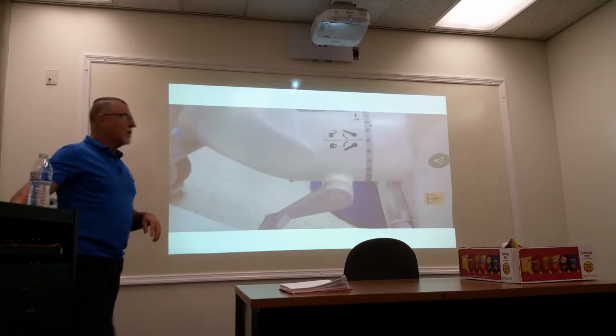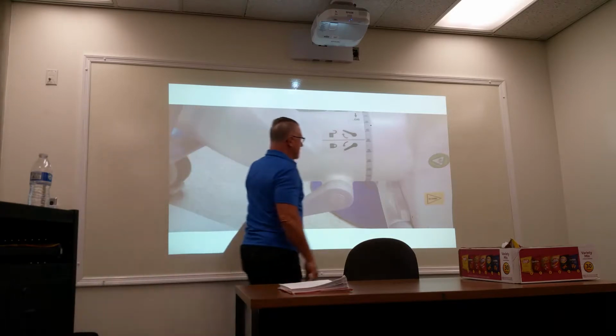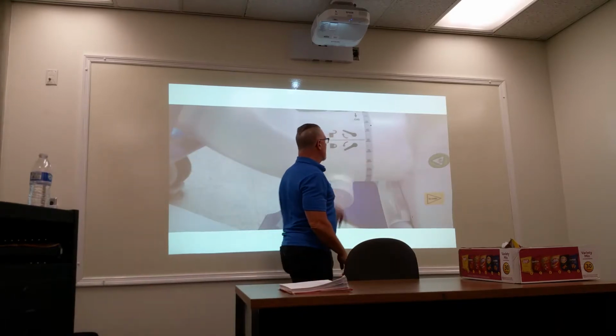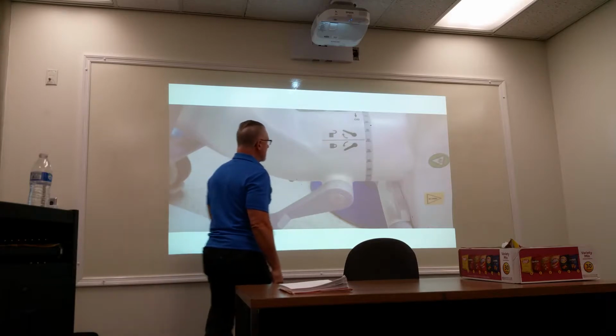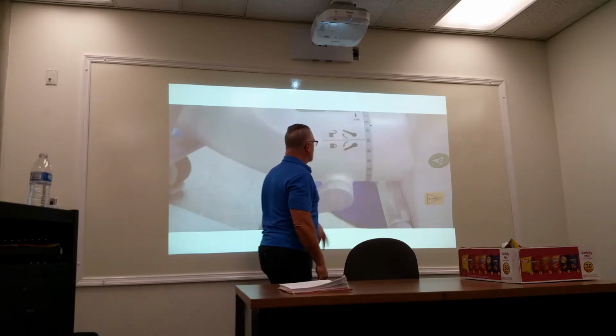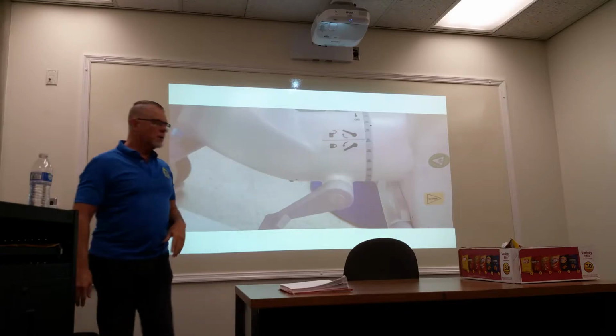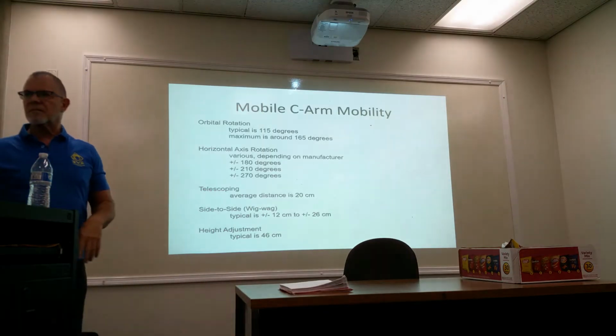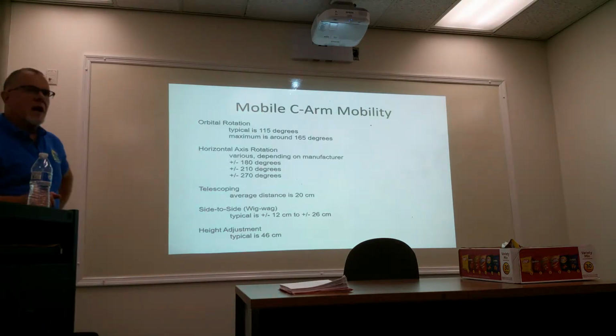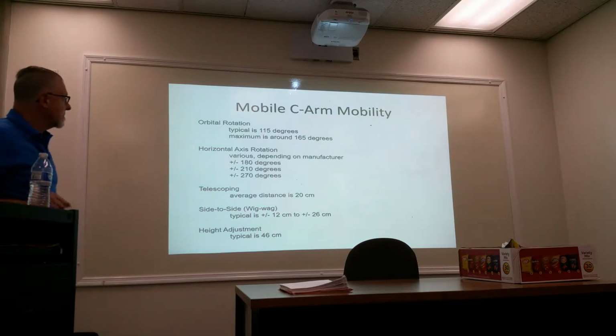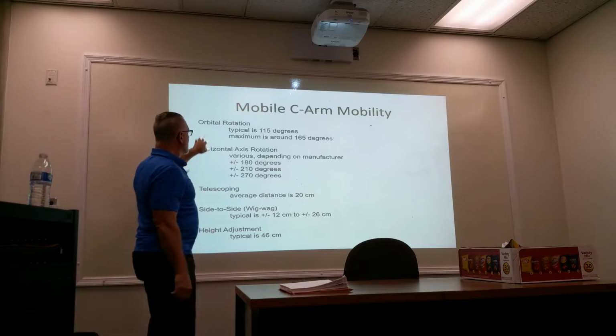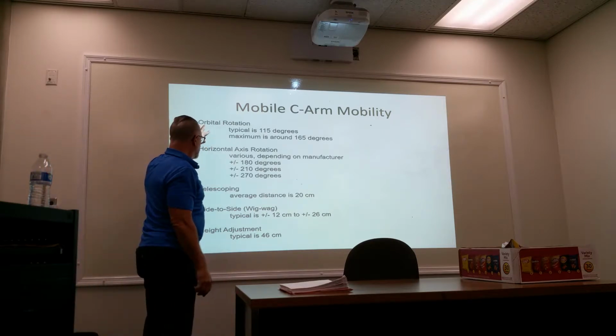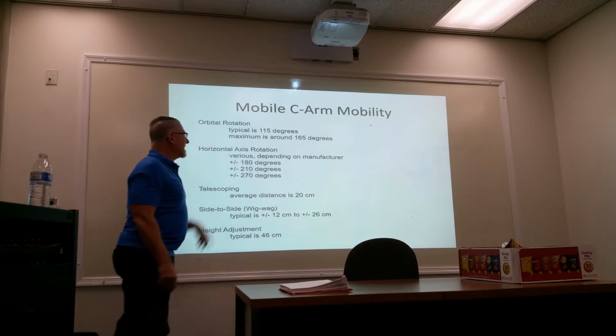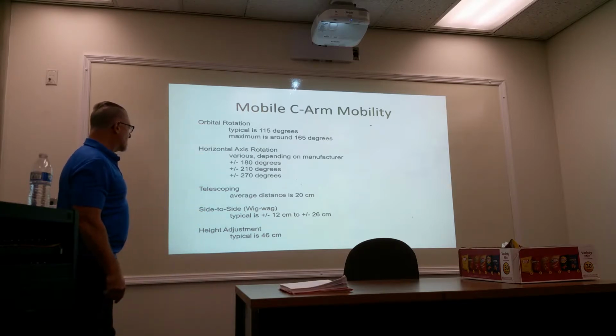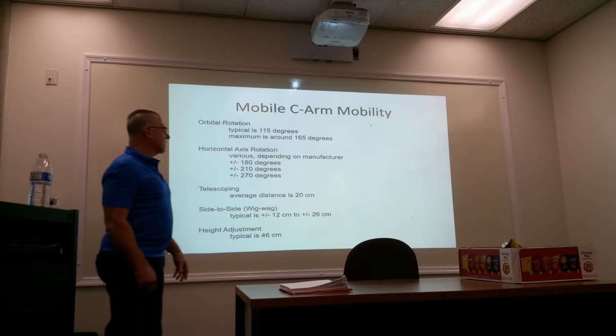Okay, so all of your locks for the most part on these pieces of equipment are manual. So this is your unlock and lock control for orientation. These are not for every single machine. This is an indication of typical. So, orbital rotation is typically about 115 degrees.